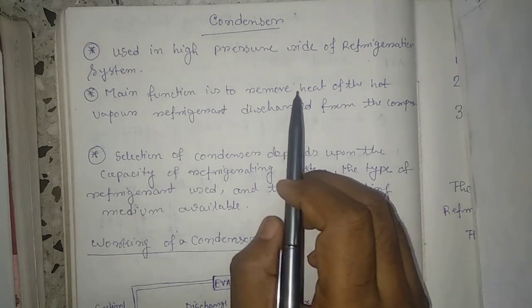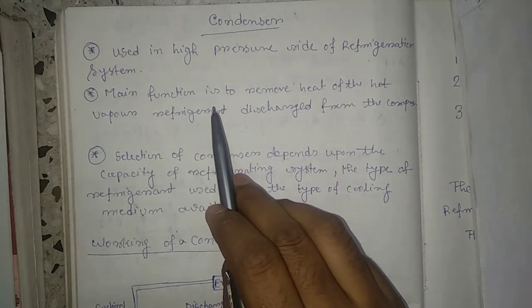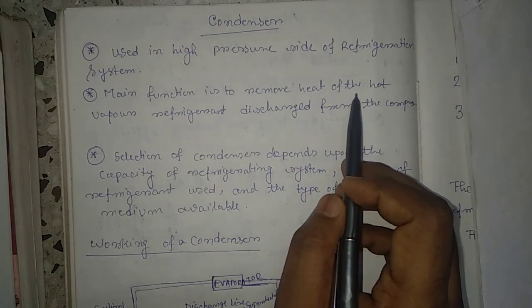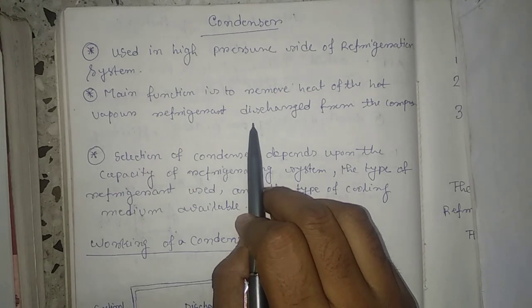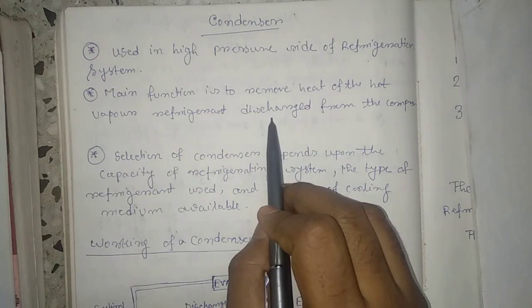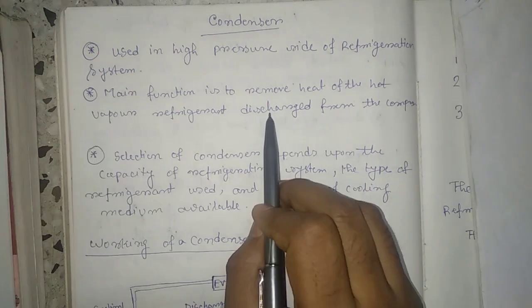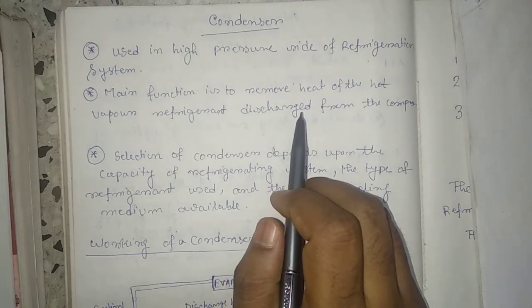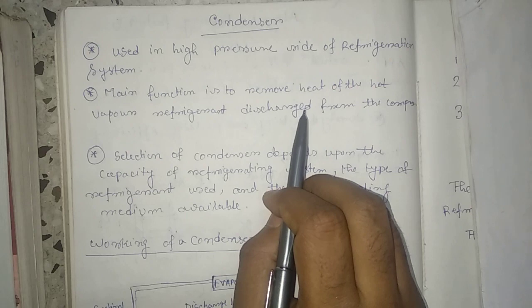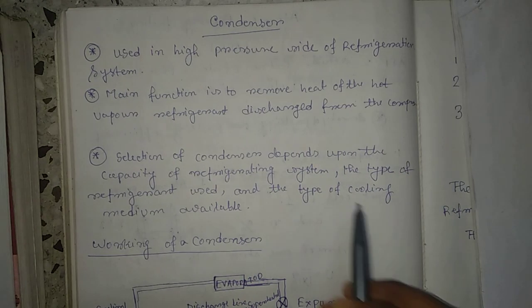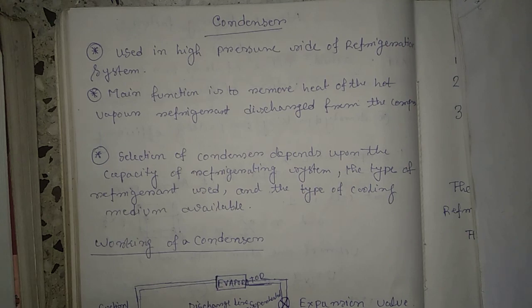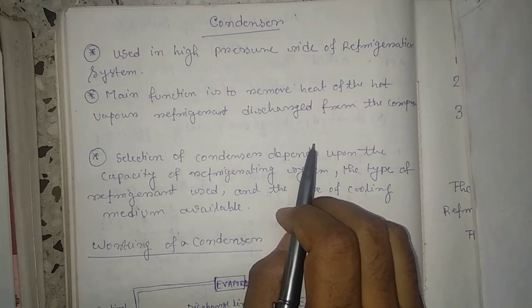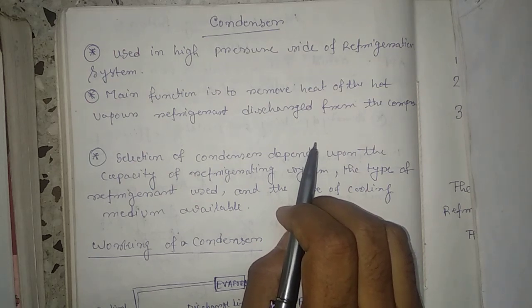The main function of the condenser is to remove heat from the hot vapor refrigerant discharged from the compressor. That vapor refrigerant is allowed to cool in the condenser. The hot vapor refrigerant contains heat absorbed by the evaporator plus the heat of compression added by the mechanical energy of the compressor motor.